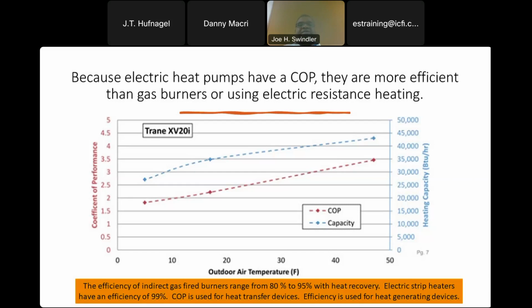The efficiency of gas-fired burners is typically around 80%, but if you use heat recovery heat exchangers, you can get all the way up to 95, 97%. And your electric heating can go up to like 99 to 100%. And keep in mind, efficiency and coefficient of performance are two different things. Theoretically, you can't have more than 100% efficiency. So COP was developed for chill water generators, for example, because you're using refrigerant to absorb heat and transfer heat. So you can get better than 100% efficiency. So that explains the difference between efficiency and coefficient of performance.